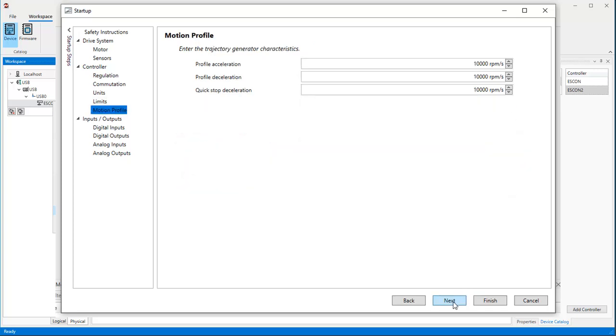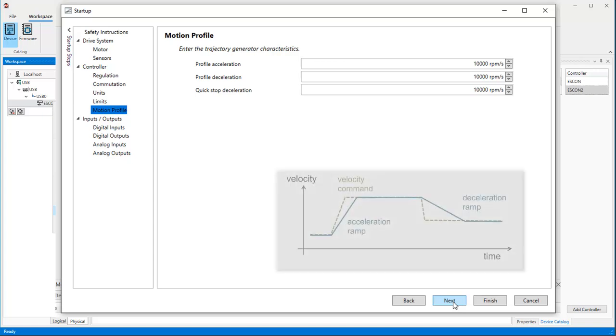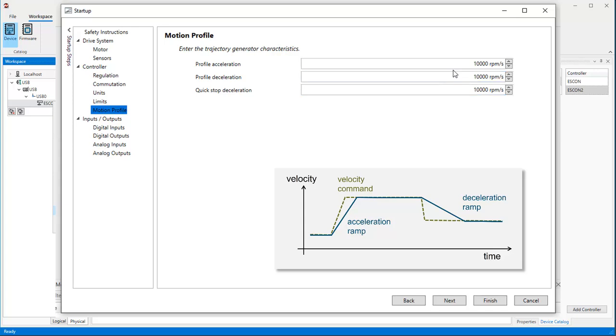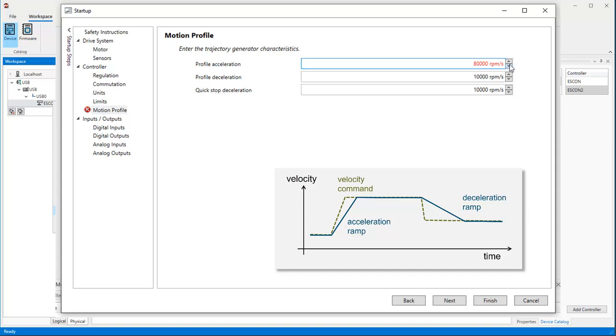Default acceleration and deceleration values for motion profiles are set to 10,000 RPM per second. When commanding new velocity values, the motor will speed up or down with these ramps. Again, it would not be able to set a higher ramp than previously specified in the limit section.